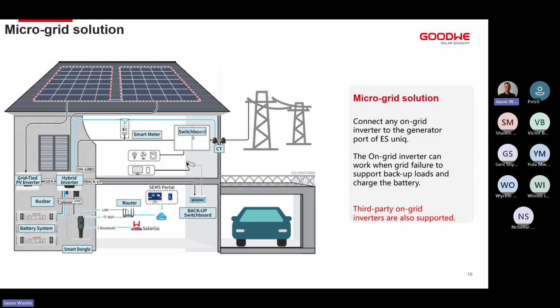The third functionality that we've got through the generator port is our microgrid solution. So through the generator port, we can connect an additional grid-tied inverter and use that for additional MPPTs to be able to run and charge your batteries. So during this, when we lose Eskom power or when we lose power from the utility, we can still power up the grid-tied inverter, create a grid reference or grid source for them, and allow the grid-tied inverter to start up and produce to either the loads or produce towards charging the batteries on the hybrid inverter. The on-grid inverter can work when grid failures happen to support backup loads and charge your batteries. And this is not specific to only GoodWe grid-tied inverters. Any third-party grid-tied on-grid inverter would also be supported.